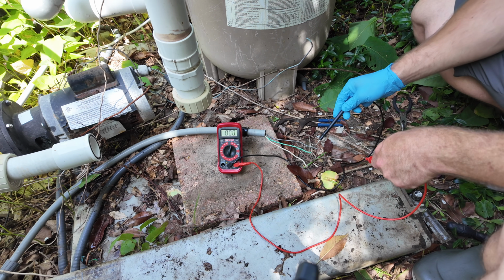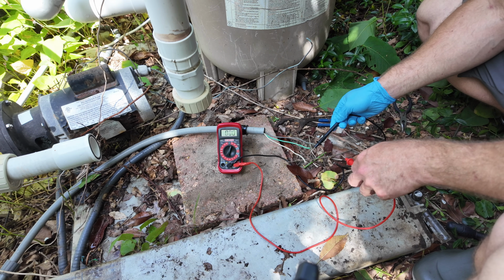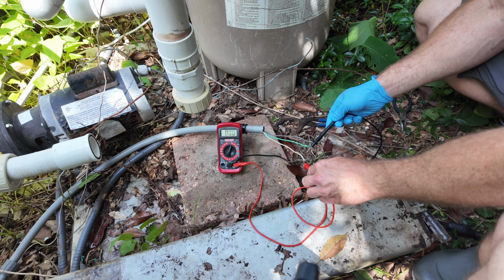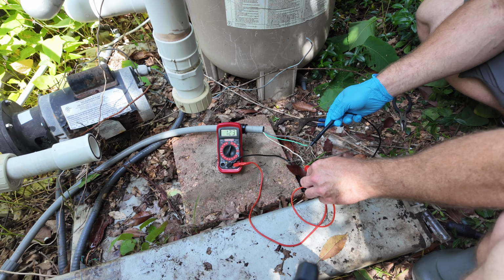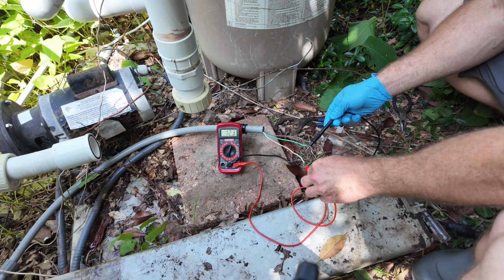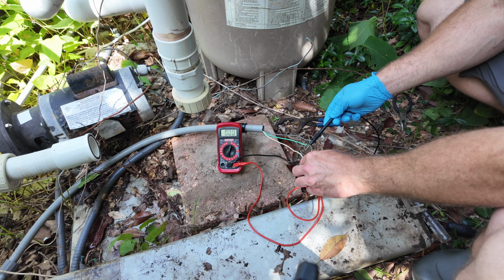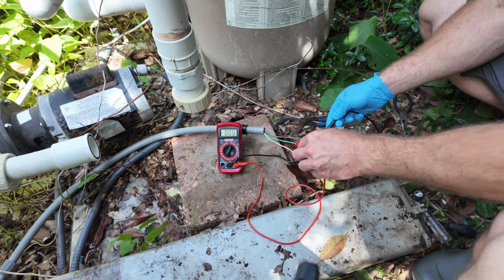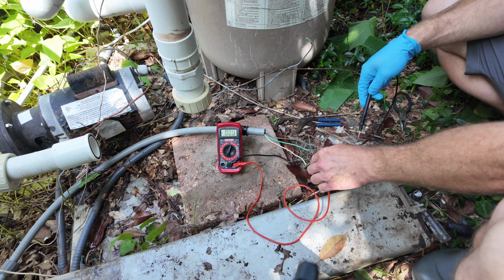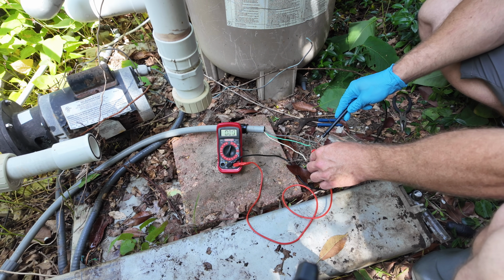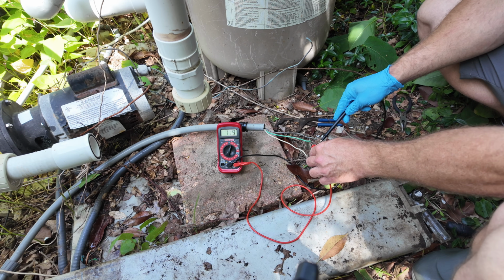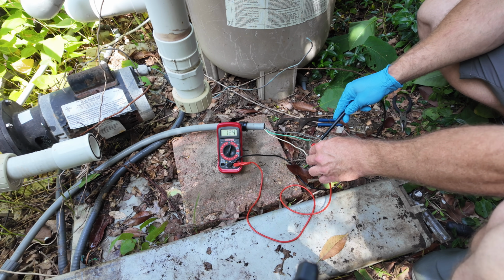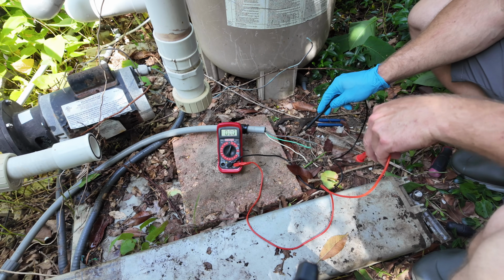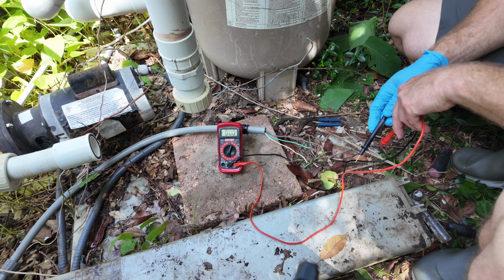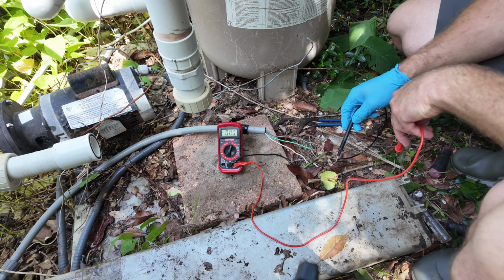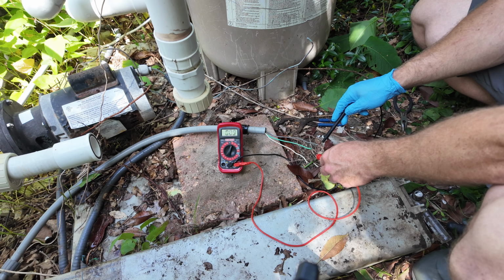You take one probe to the ground wire, which is the green one, and the other probe to, let's say, the white wire, and I'm getting 120 volts, which means this white wire is a hot wire. Now I do the same thing with the green wire and the black wire, and I'm also getting 120 volts. That tells me both wires are hot wires, each delivering 110-120 volts.